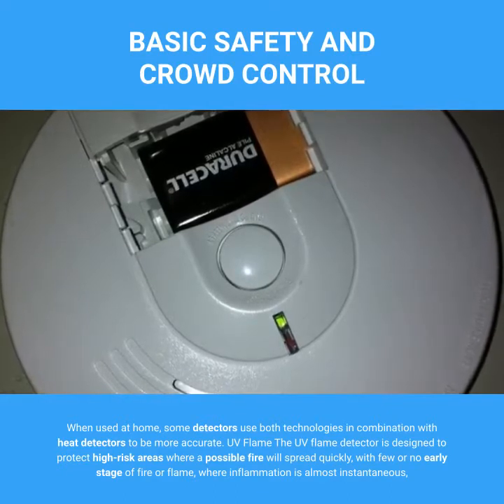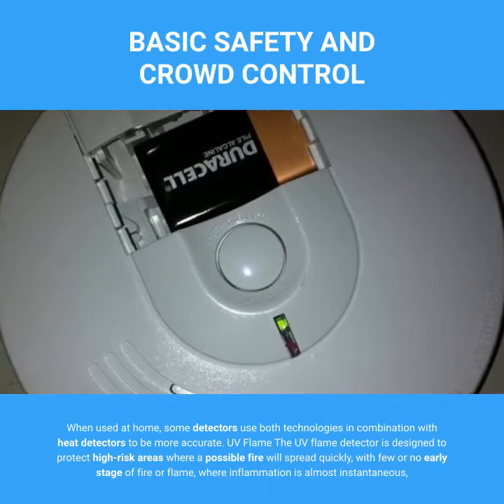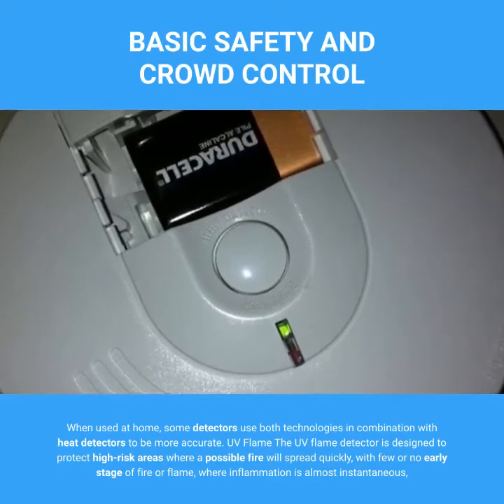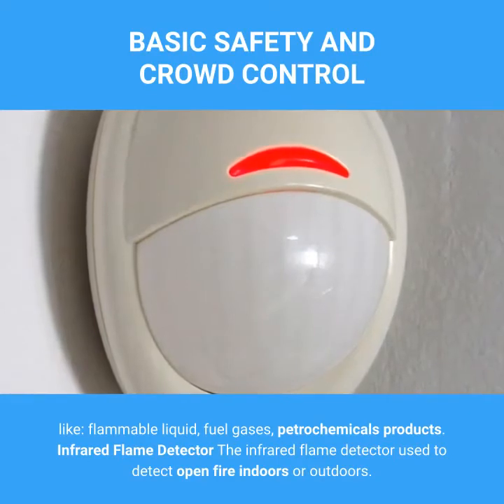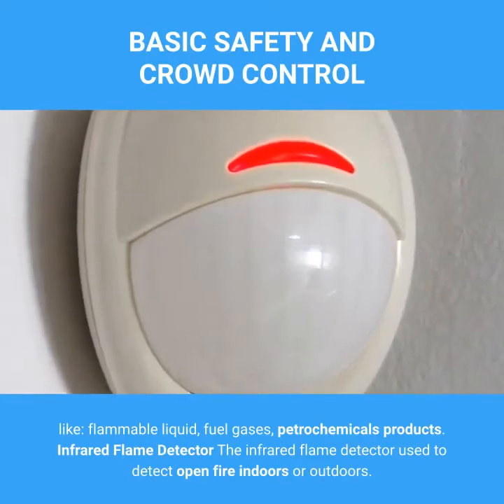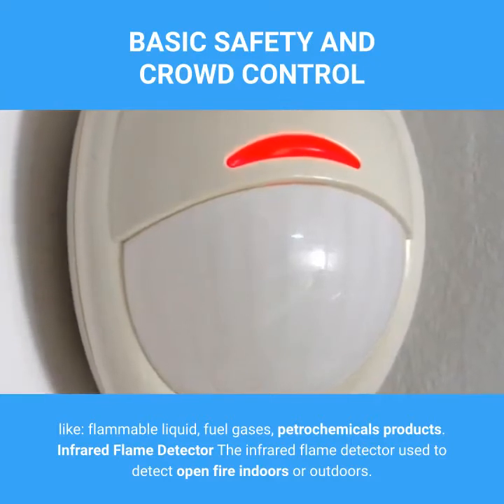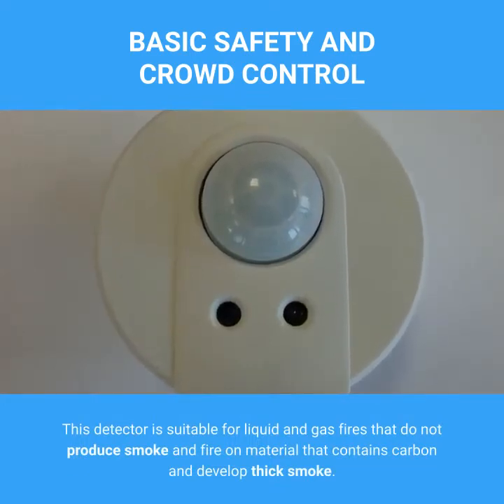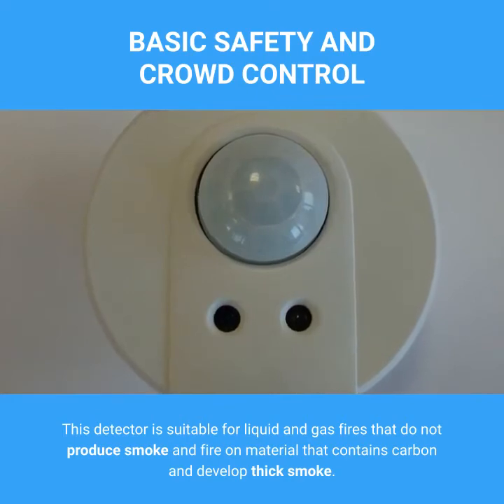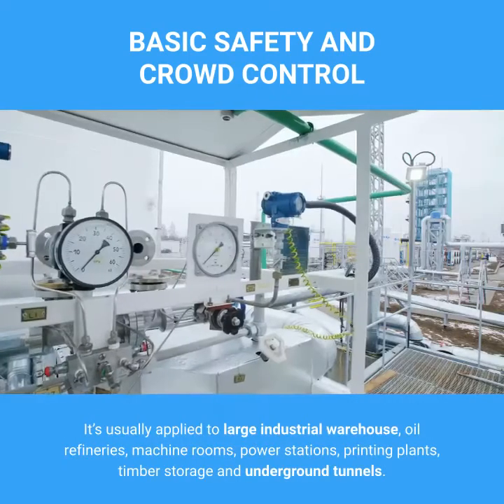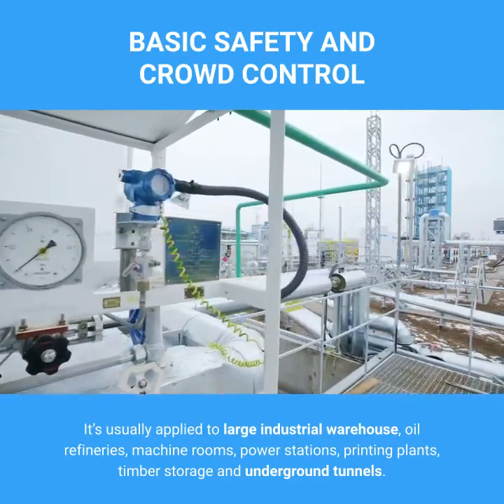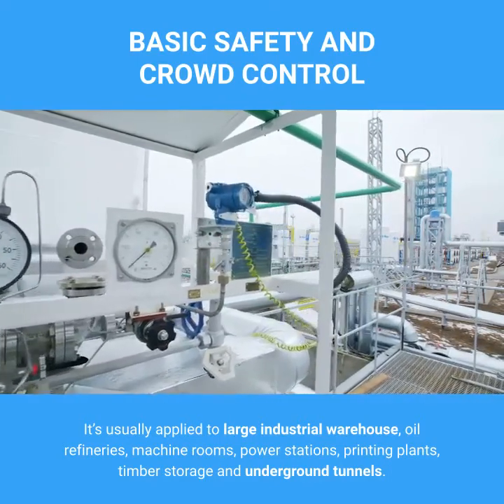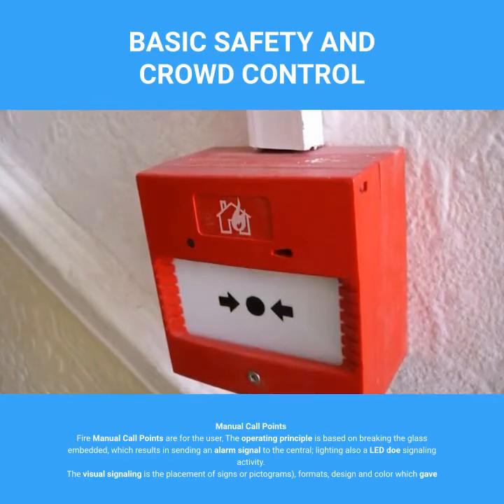UV flame detector: The UV flame detector is designed to protect high-risk areas where a possible fire will spread quickly, with few or no early stages of fire or flame, where inflammation is almost instantaneous — such as with flammable liquids, fuel gases, and petrochemical products. Infrared flame detector: The infrared flame detector is used to detect open fire indoors or outdoors. It is suitable for liquid and gas fires that do not produce smoke and fires on material that contains carbon and develops thick smoke. It is usually applied to large industrial warehouses, oil refineries, machine rooms, power stations, printing plants, timber storage, and underground tunnels.